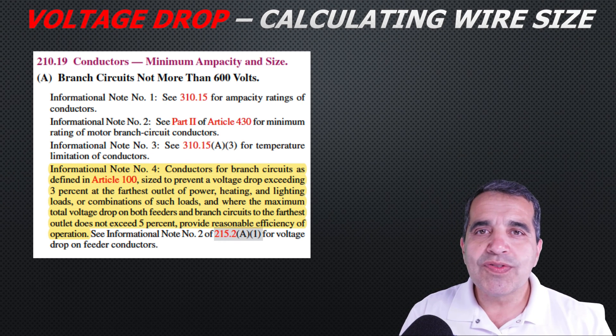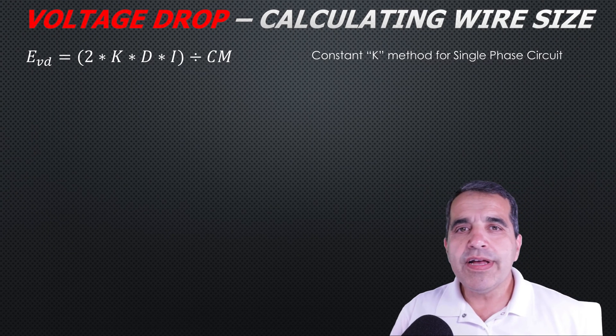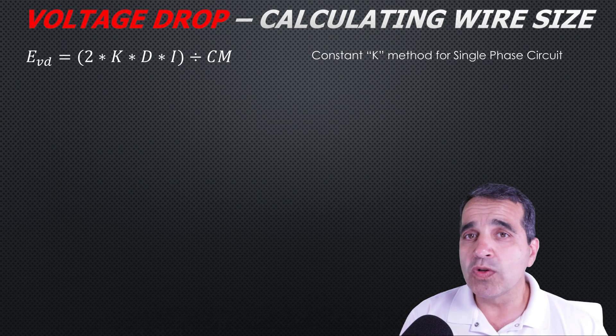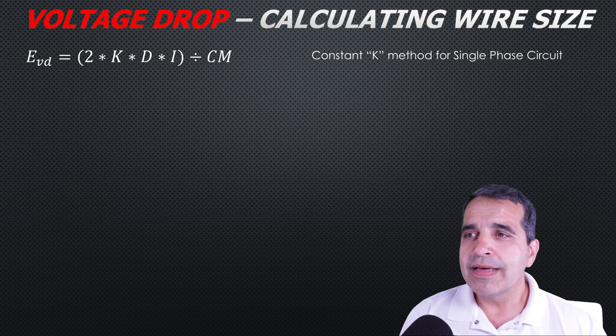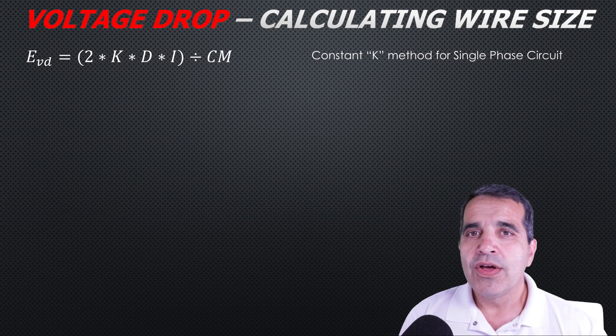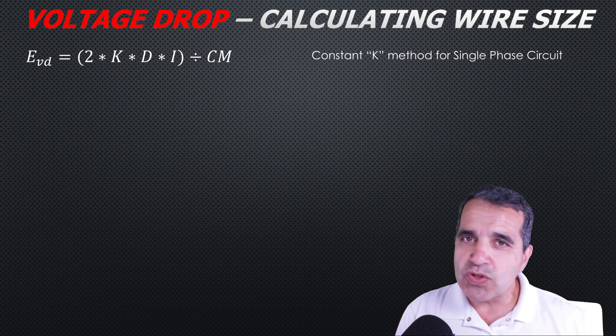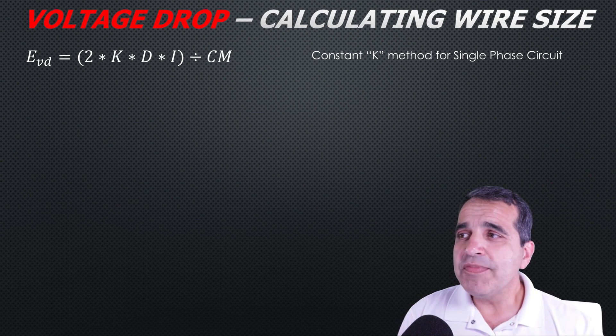So how do you use the National Electric Code to calculate voltage drop? Here is the formula: voltage drop E equals two times K times distance times amperage, divided by circular mils. The number two is for a single-phase circuit, because you have a hot conductor going out and a neutral coming back — two conductors total.